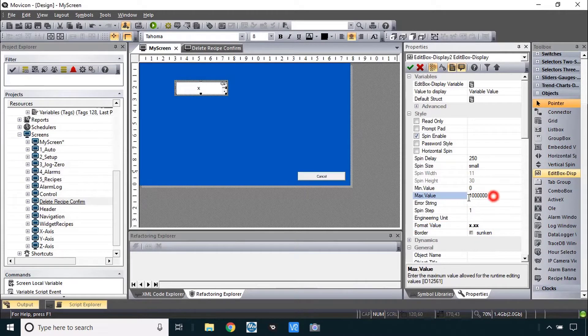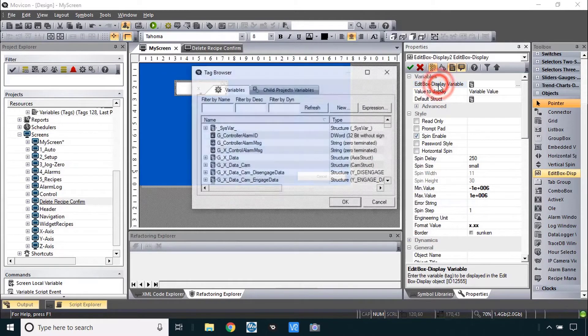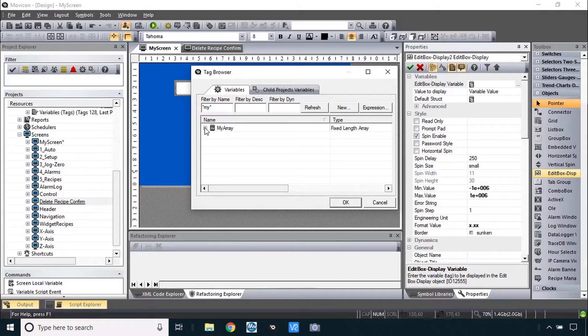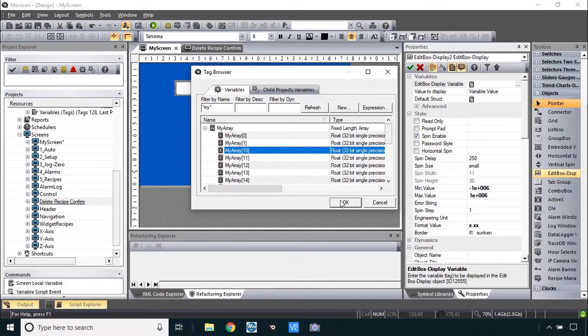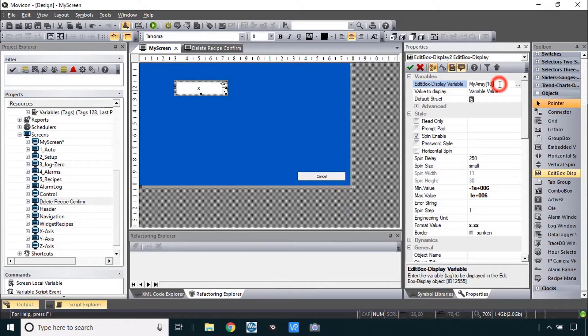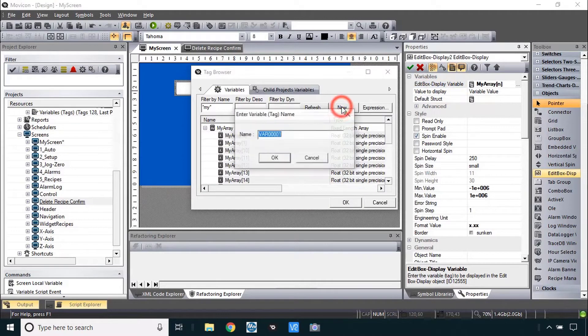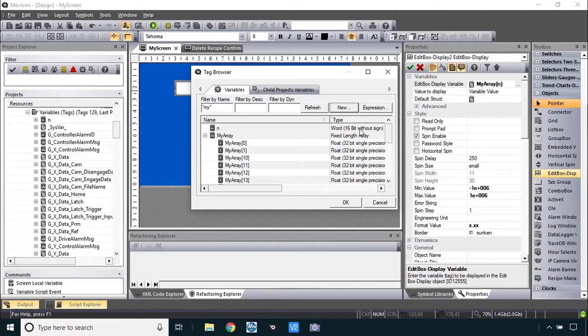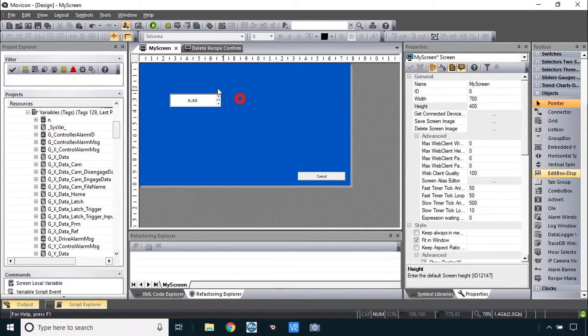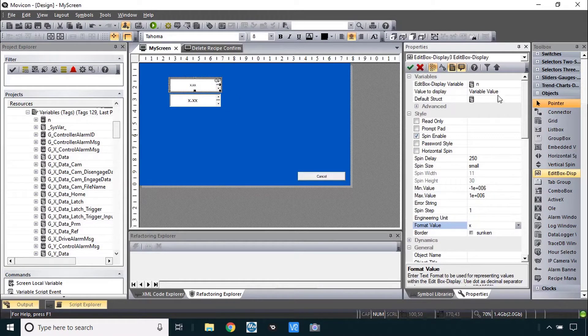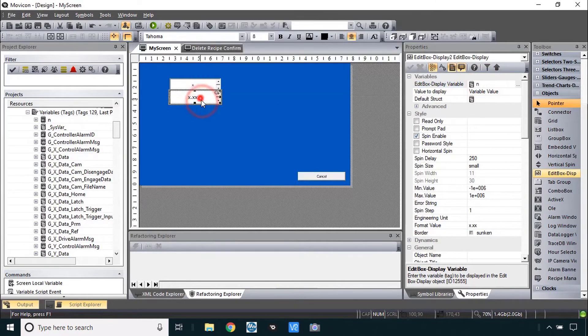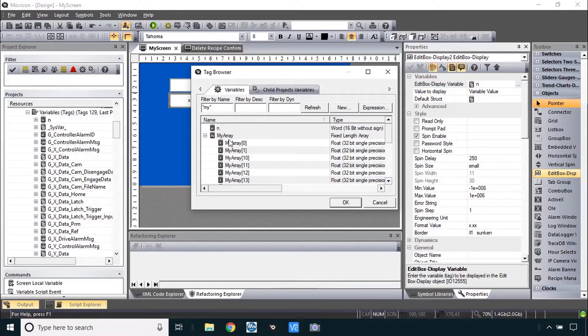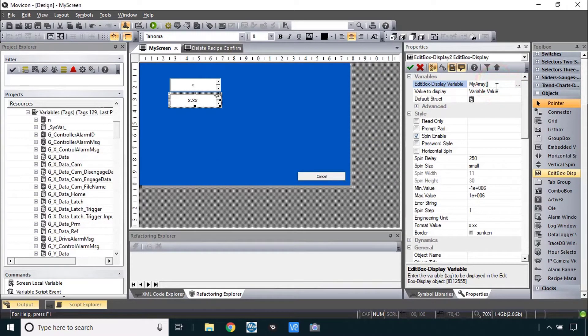Now let's put some of this data in an edit box display from the array. It's a float so I'll give it a format value that includes decimal places. I'll set max and min values with a negative so we can go plus and minus. For the edit box display variable, I'll select 'my array' and choose element number 10. But the beauty of arrays is you don't have to leave the array element as a fixed value — you can put a variable in there. So I'll create a new variable called 'n' with a word data type, show variable n in a separate edit box display, and link the first display to my array element number n.